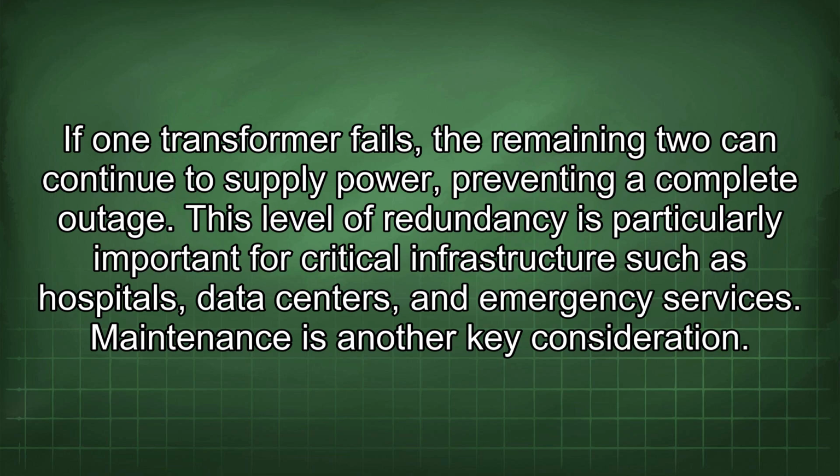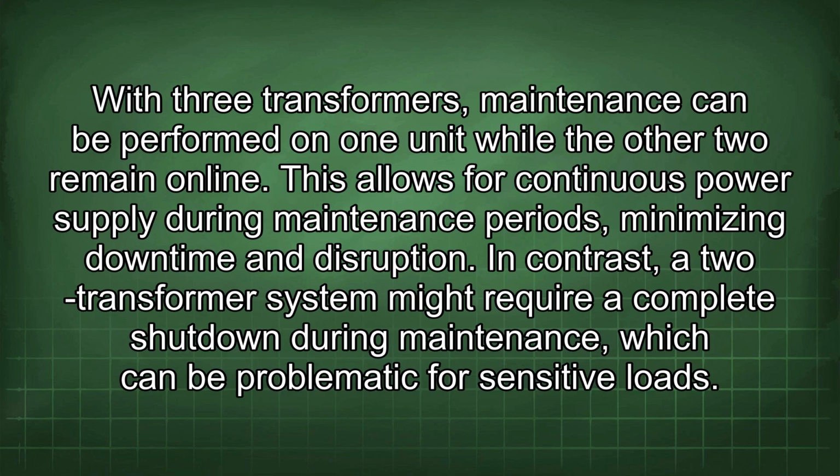Maintenance is another key consideration. With 3 transformers, maintenance can be performed on 1 unit while the other 2 remain online. This allows for continuous power supply during maintenance periods, minimizing downtime and disruption. In contrast, a 2-transformer system might require a complete shutdown during maintenance, which can be problematic for sensitive loads.